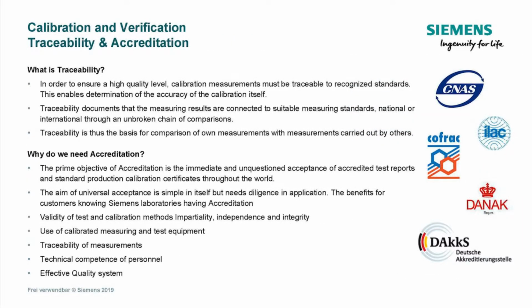What is traceability? In order to ensure a high quality level, calibration measurements must be traceable to recognized standards. This enables determination of the accuracy of the calibration itself. Traceability documents that the measuring results are connected to suitable measuring standards, national or international, through an unbroken chain of comparisons. Traceability is thus the basis for comparison of own measurements with measurements carried out by others.